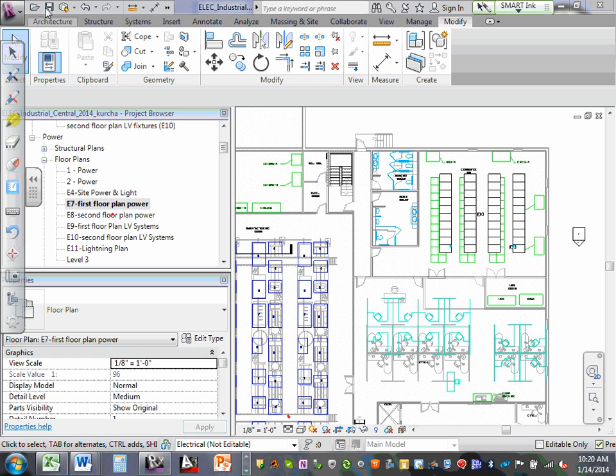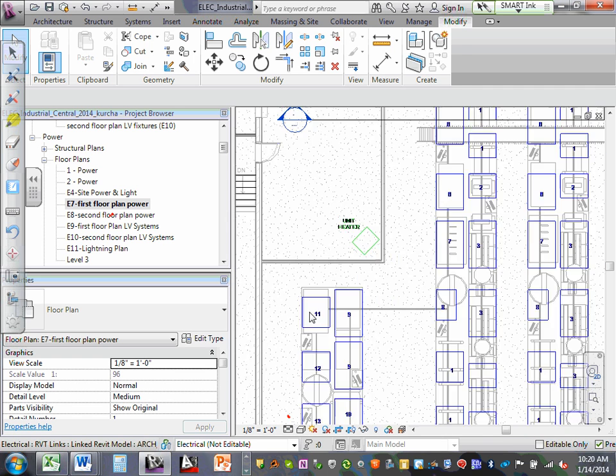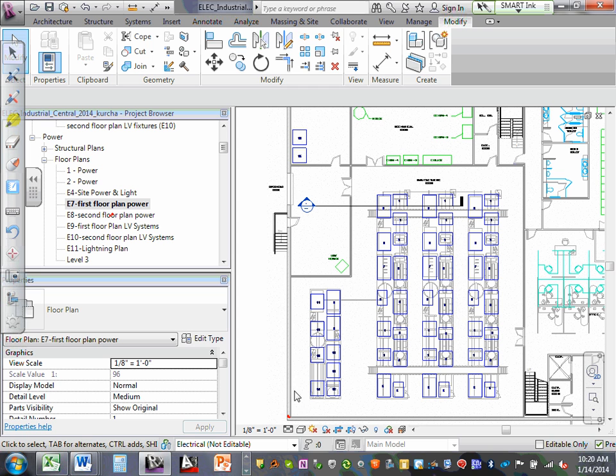the computer room, I'd lay out a couple of horn strobes in there that again are for evacuation purposes, because you have IT guys that are in there all the time. And if you get a general building fire alarm, they need to know the building is on fire. So, manufacturing, same thing.